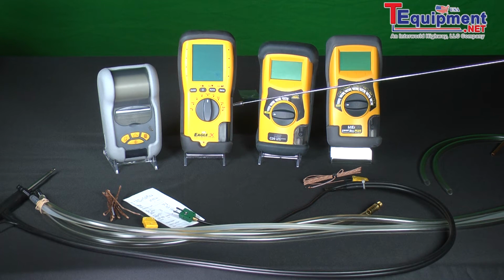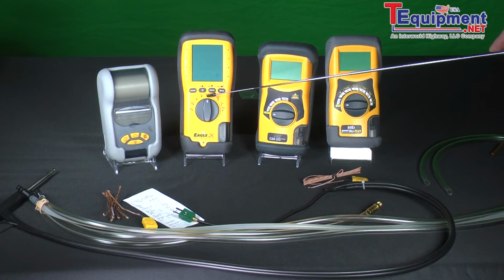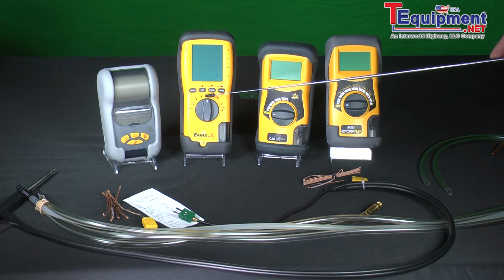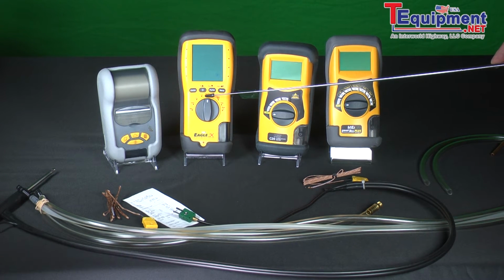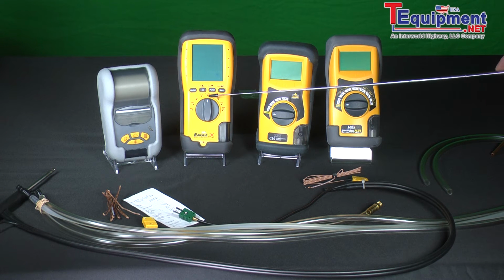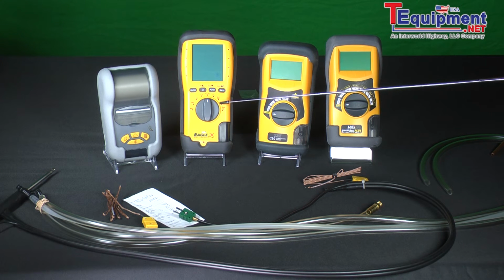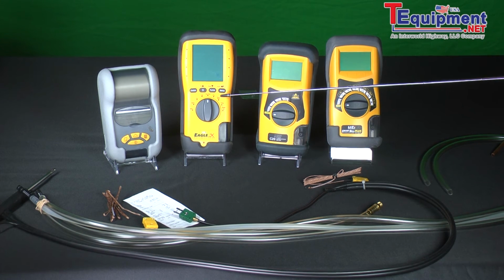You then have a status, you have auxiliary, and then you go into the fuel selection. So based on what your fuel is, you will select whether it's natural gas, propane, light oil, heavy oil, wood, or biofuel. You then have the flue gas or combustion test. You then have the pressure test. We have a cracked heat exchanger test, the temperature test or dual differential temperature, and we have a room CO test that runs for 30 minutes.